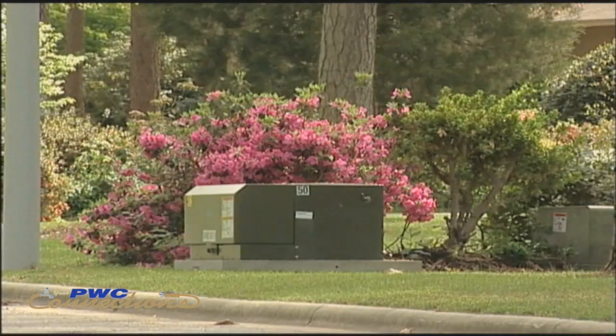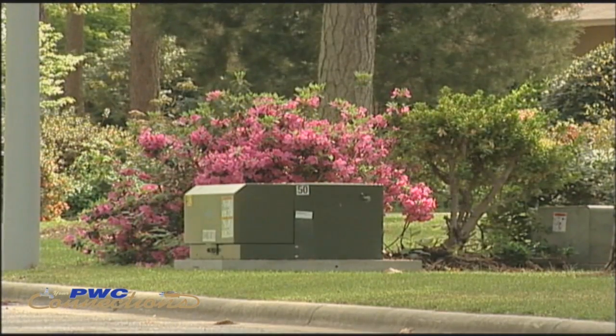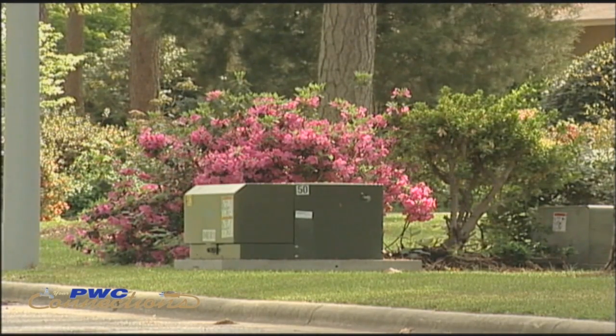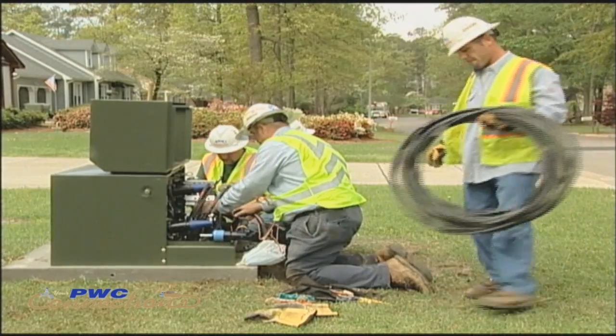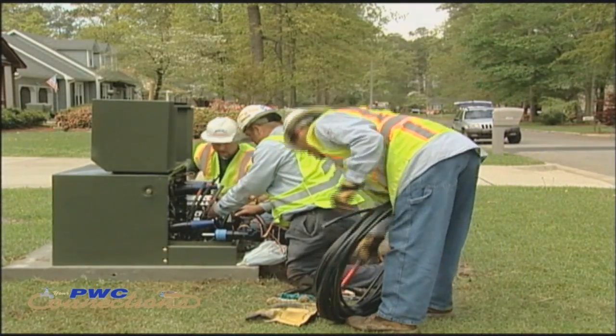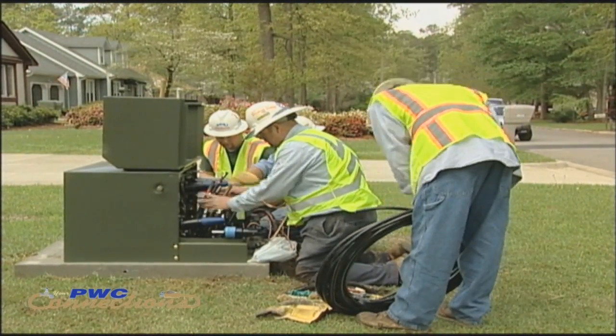We've set transformers before where people ask us, 'That's an ugly green box in my yard, I'm gonna plant trees around it.' And we say, well, you can, but no matter how good they look, we're going to have to pull them up, because we need at least 9 feet in the front to operate what's called a shotgun stick, to safely pull the wires off the elbows and plug them back on.